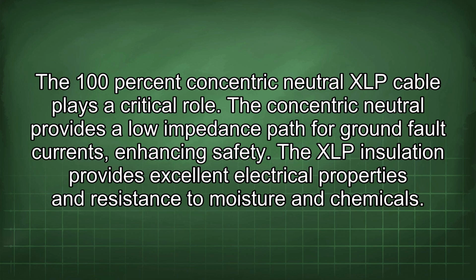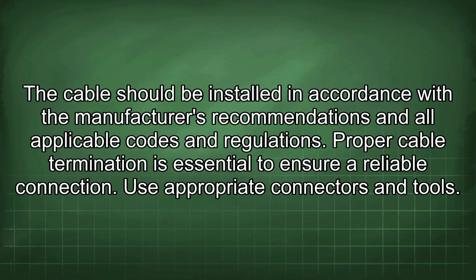The 100% concentric neutral XLP cable plays a critical role. The concentric neutral provides a low impedance path for ground fault currents, enhancing safety. The XLP insulation provides excellent electrical properties and resistance to moisture and chemicals. The cable should be installed in accordance with the manufacturer's recommendations and all applicable codes and regulations. Proper cable termination is essential to ensure a reliable connection.